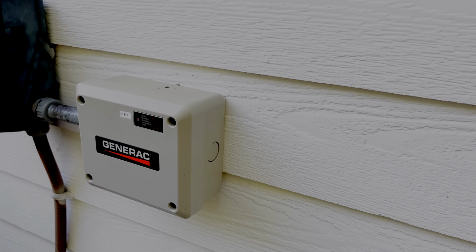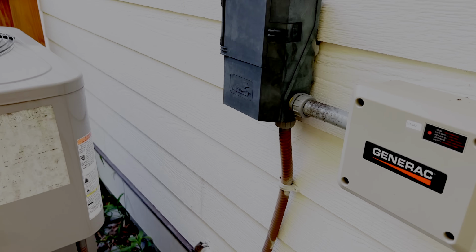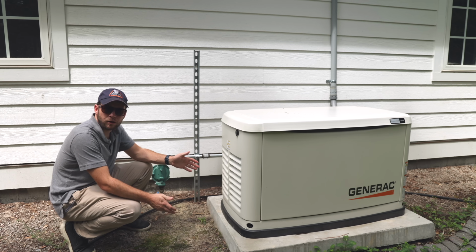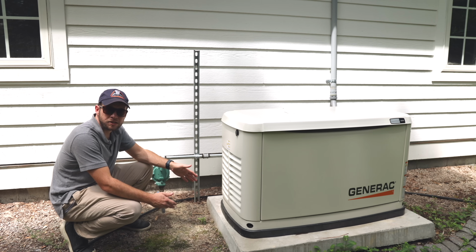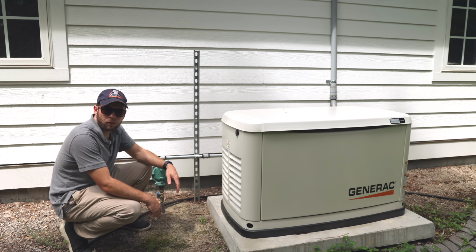and they have devices on them that are known as load shedders. Essentially, what they do is they watch the frequency of the generator to make sure that the engine is not struggling. If an engine gets loaded down too much by the generator, the hertz can drop, or the frequency of the AC electricity. And when that happens, the load shedder is going to notice, and it's going to disconnect that load to make sure that you've got enough power for other priority devices in your house. So you set the priority on each of the load shedders as to when it's going to kick off, and then it can just automatically take care of the loads so that the rest of your house can stay powered.